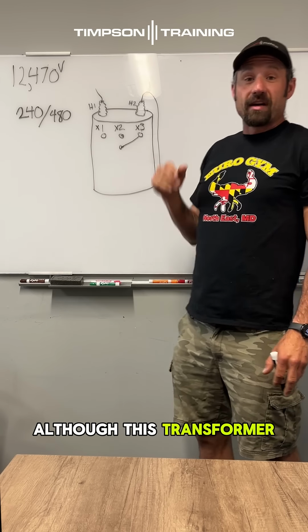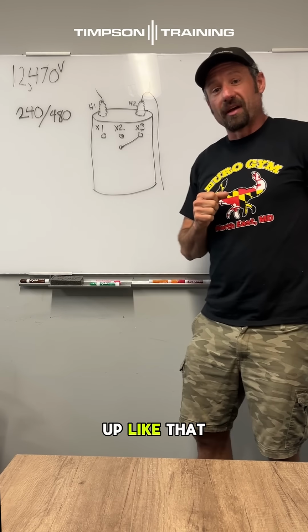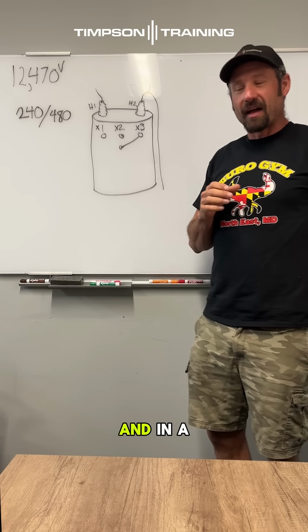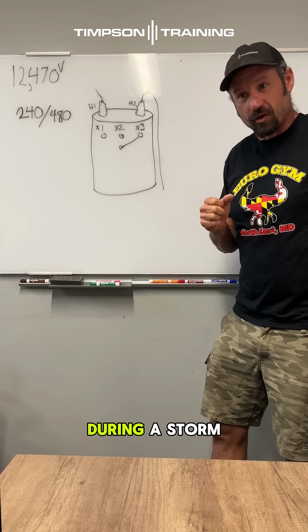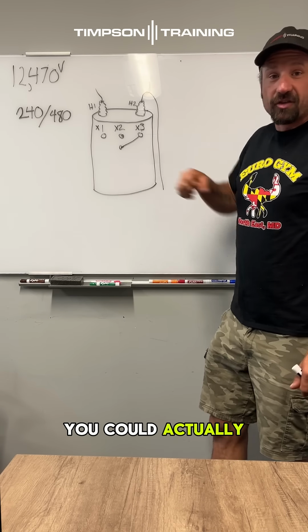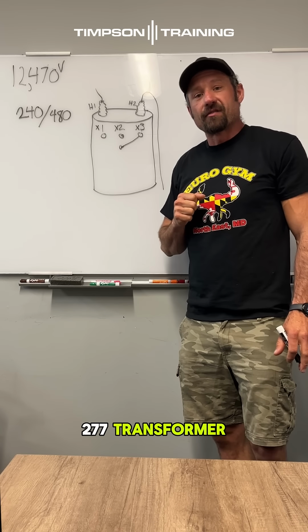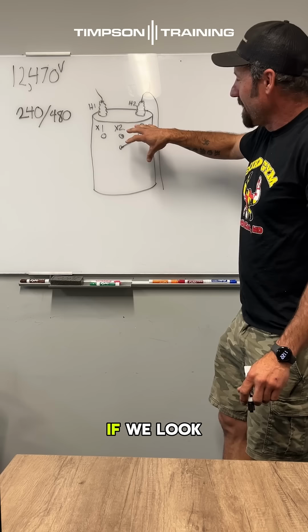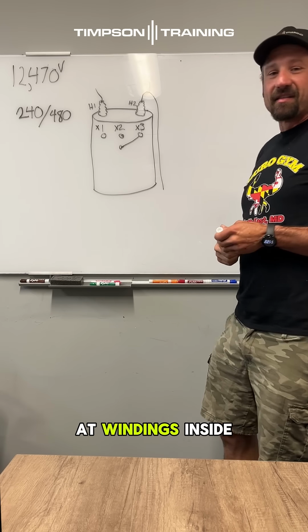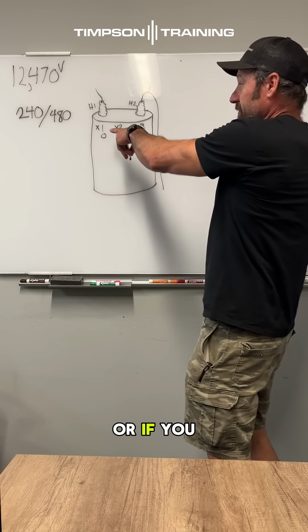Although this transformer was never meant to be hooked up like that, it absolutely works. In a pinch during a storm, you could actually just put a regular 277 transformer up there to get them back in power. If we look at the windings inside this transformer, or just look at the 240/480...